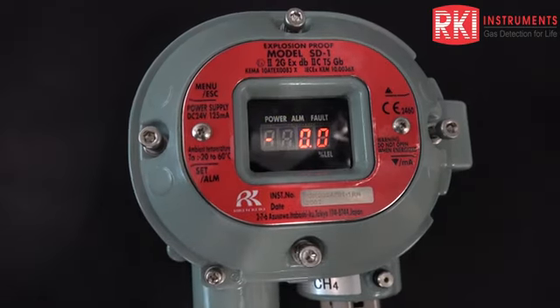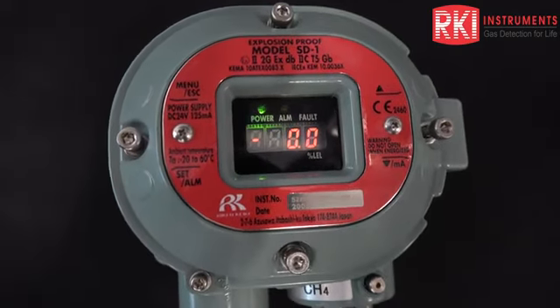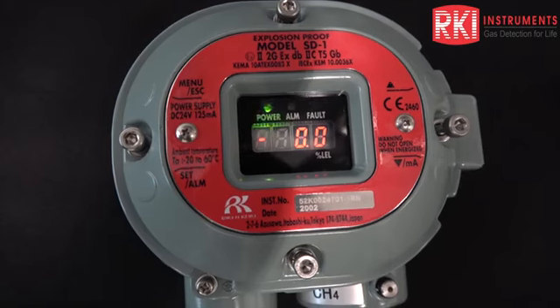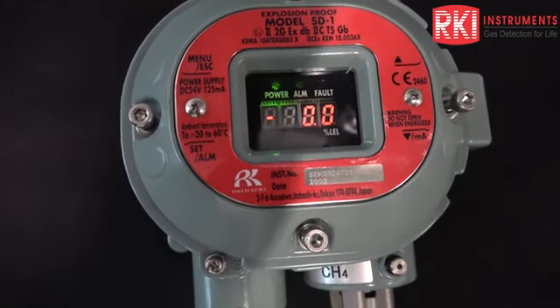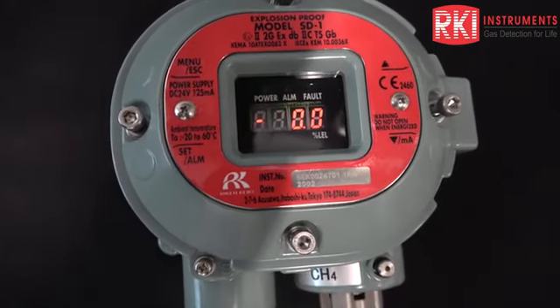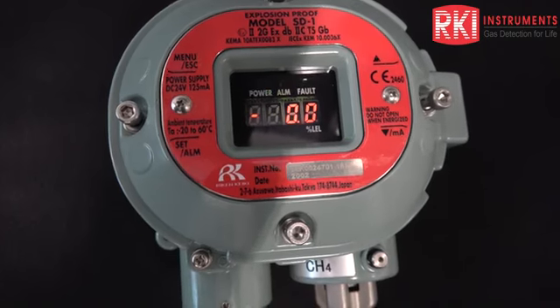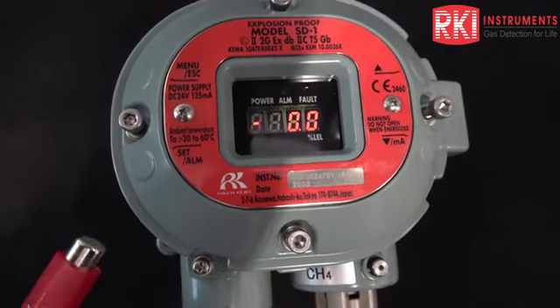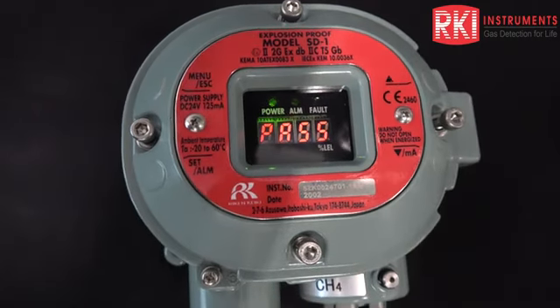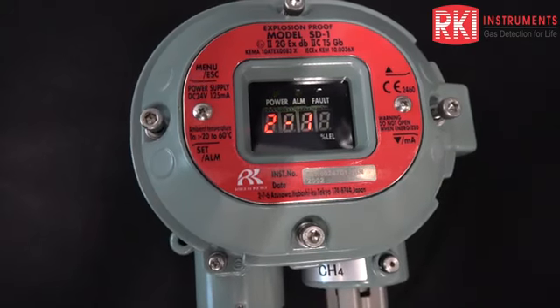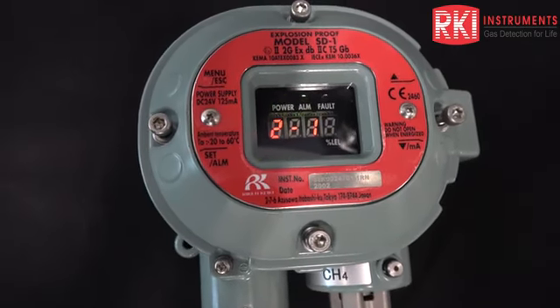And now I will touch the set pad over here on the lower left. Okay, and now it shows minus 0.0, and that's fine. It might be a value that's a little bit elevated, a little bit low, or a little bit negative. That doesn't really matter too much. And then at this point, what I want to do is touch the pad again. And then you want the word to say cal, and then it'll say pass. Okay, so there we passed our air adjustment to the gas-free atmosphere.